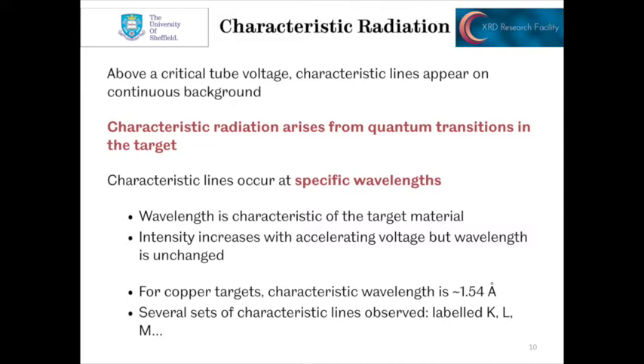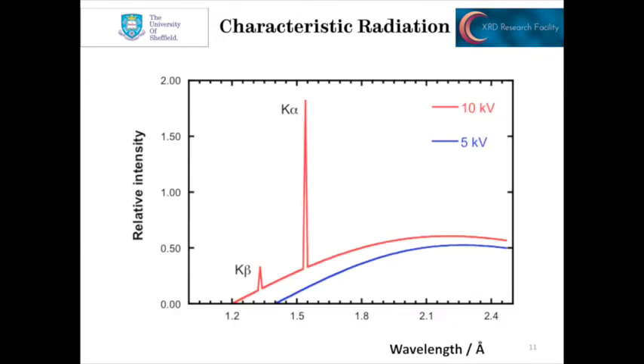We see various different characteristic lines, which we call K, L, M, and so on. When we are below the critical voltage — for example, 5 kilovolts — we don't have any characteristic radiation being produced. When we increase the tube voltage to 10 kilovolts, we start to see the K-alpha and K-beta lines emerging.